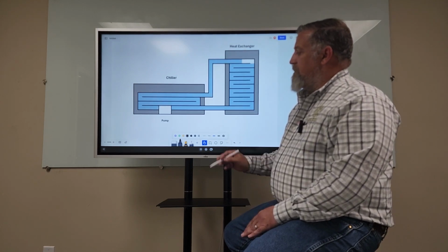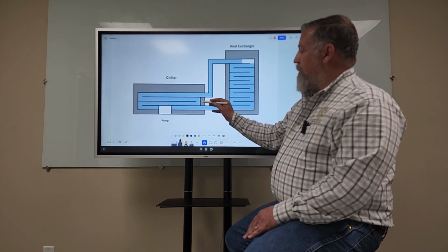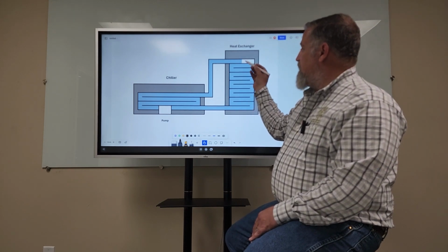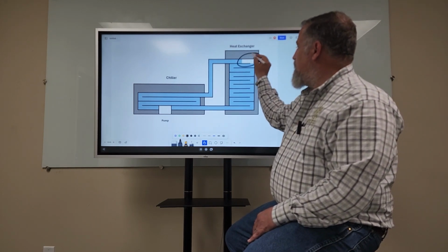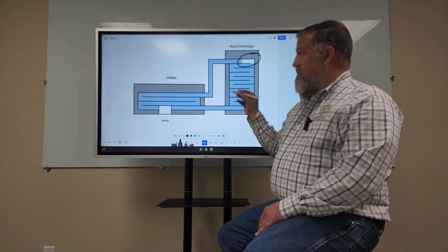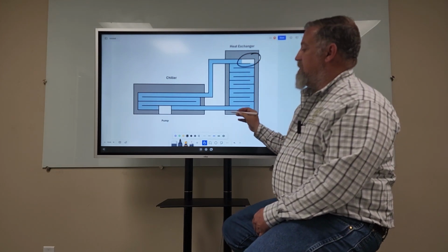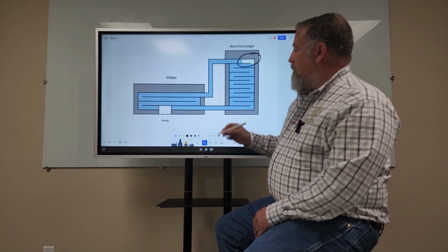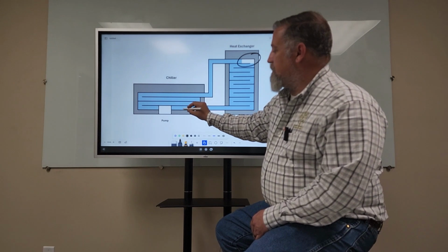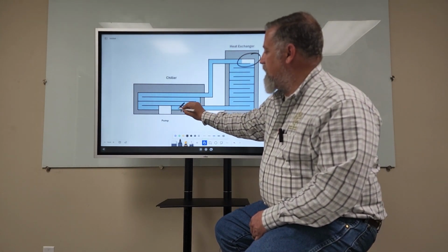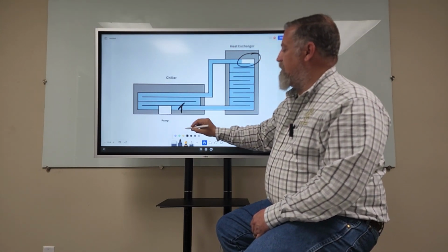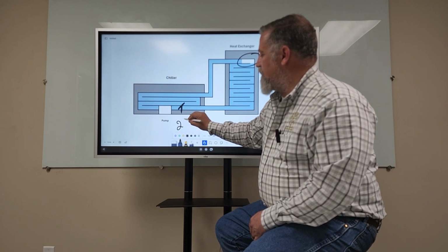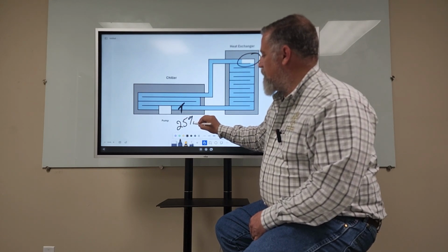Now, once we believe that our fill process is complete, we want to do a few things. You can see here that I've added in a small air pocket that's still trapped in the heat exchanger. So in order to get this out, we've got to move it. So we're going to reduce our triple duty valve, which we'll put our triple duty valve rail right behind the pump. We're going to reduce that down to 25%.